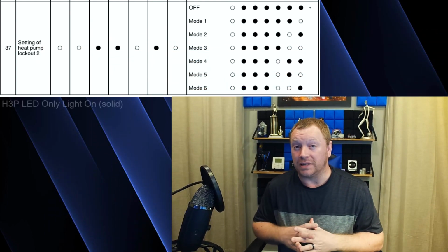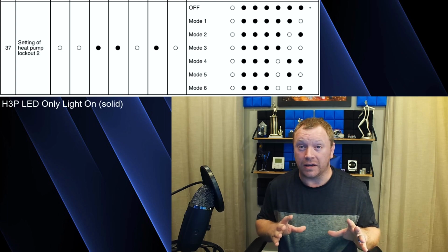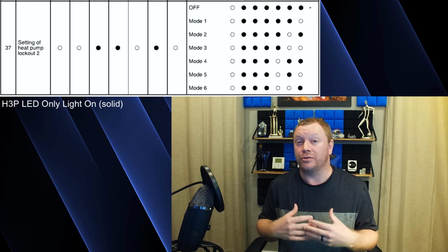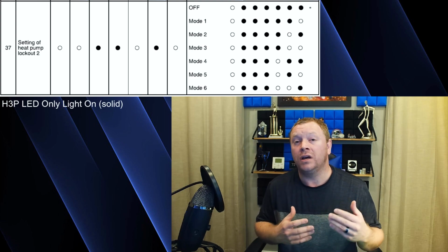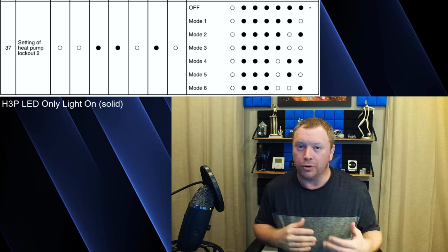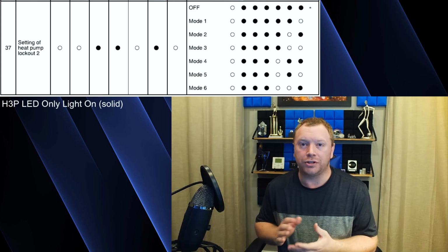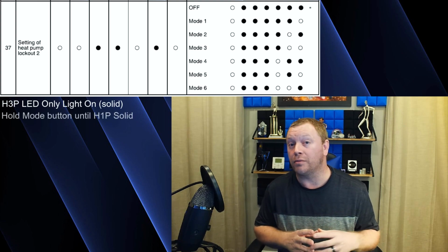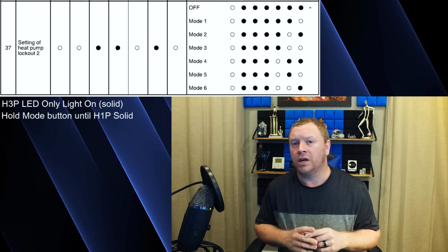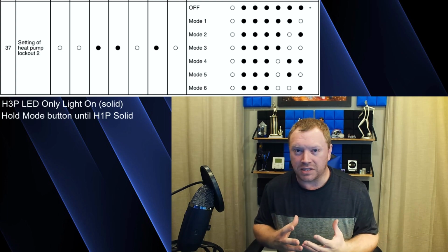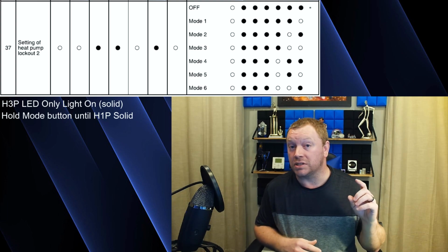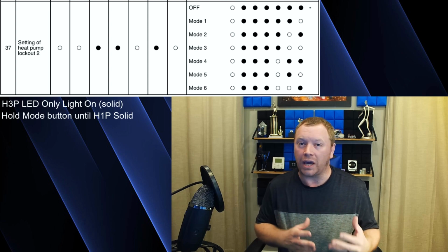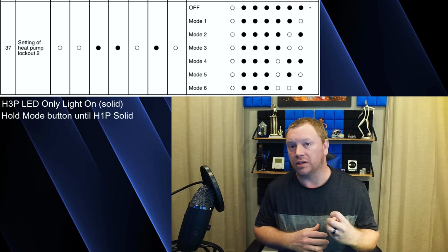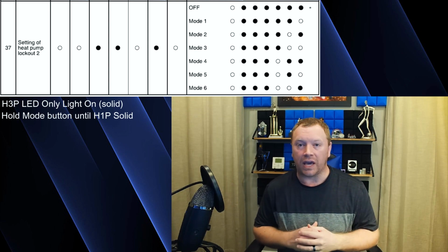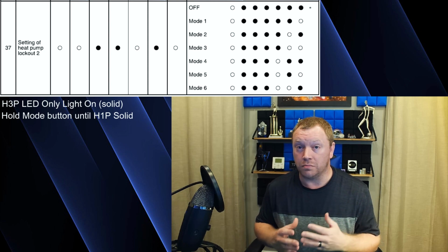First, you need to make sure the outdoor unit H3P light is the only light on and solid. That indicates that the outdoor unit is at the main screen. And then you need to go into what's called mode 2 or service mode 2. And you do this by pressing and holding the mode button at the outdoor unit. This usually takes about 5 to 6 seconds, but what I always tell my guys is press and hold the mode button until H1P is solid on.